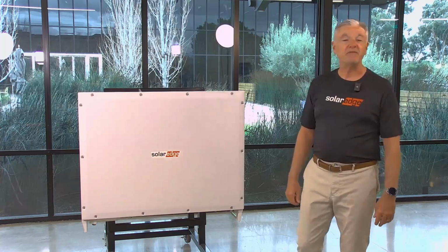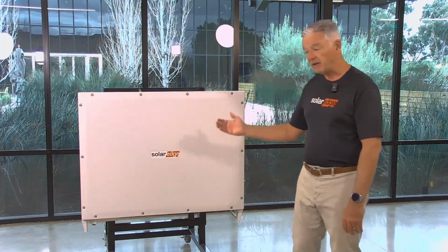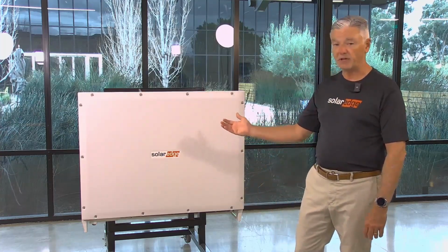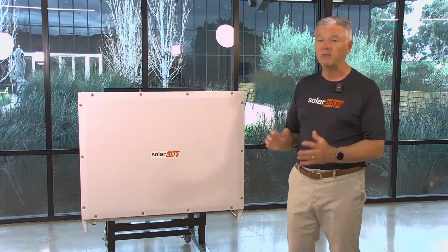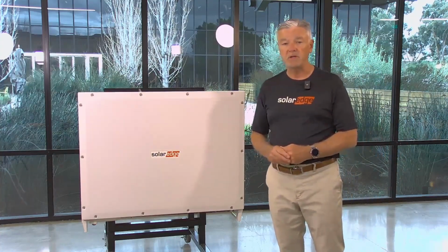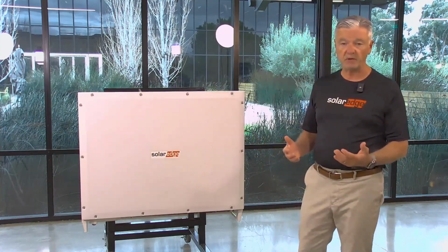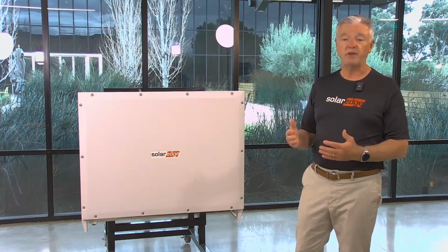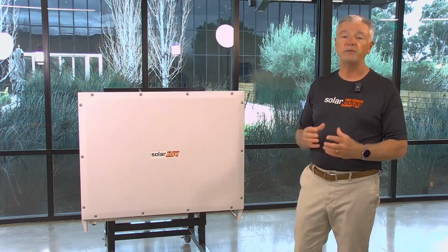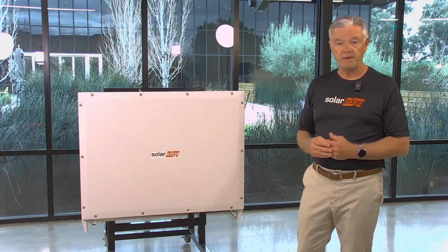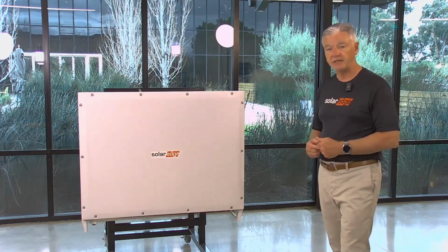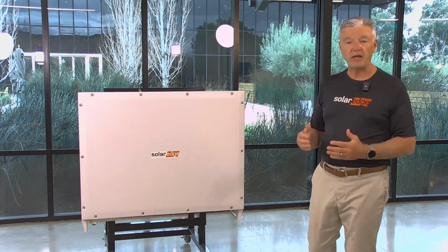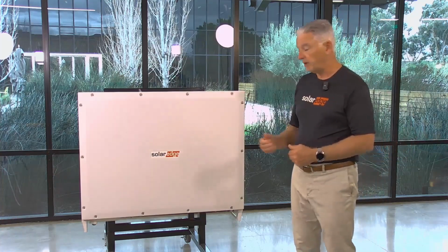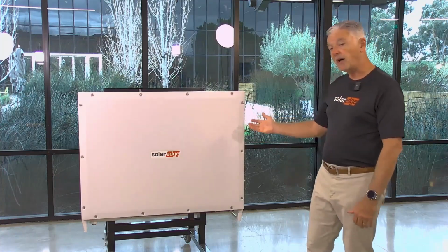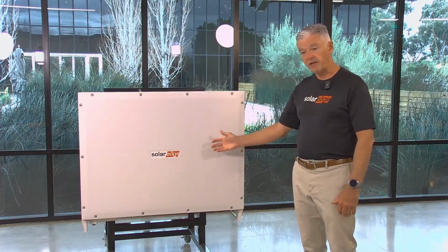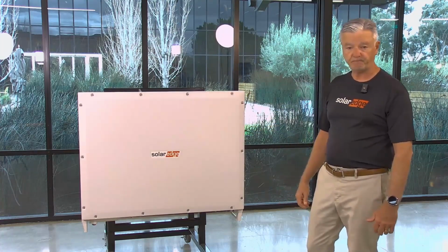Some specifications and features that are important. On a high level, the inverter is rated at 330 kilowatts AC. That makes it one of the highest rated inverters on the market. It's a 1500 volt DC inverter. During operation, it uses a fixed input voltage of 1250 volts DC. The AC voltage is 690 volts AC. That makes it an 800 volt class rated inverter. The inverter measures 43 inches wide by 36 inches tall, and it weighs 386 pounds.